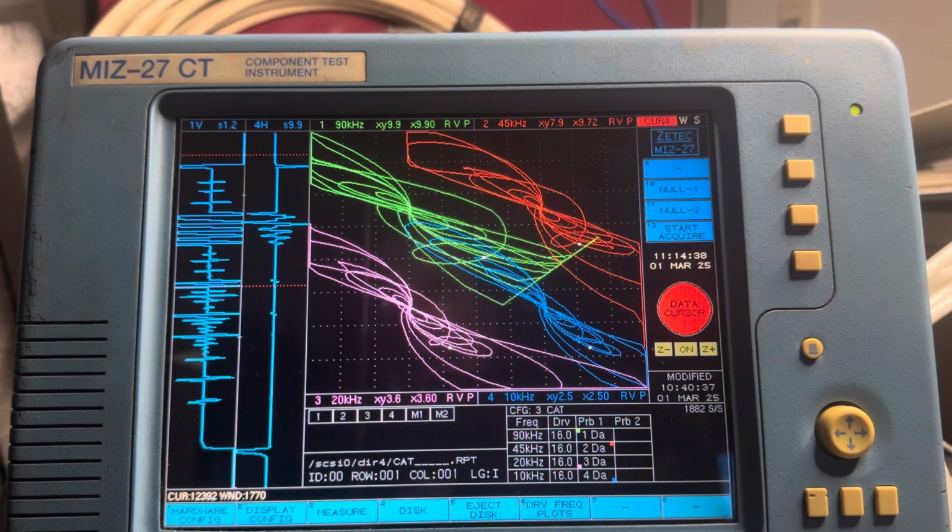The phase and amplitude of your signal is also related to the weighted average of all disturbed eddy currents at all depths. What that means is if you have an eddy current event right at the surface, you're going to have a signal with a phase angle that's closer to 0, or closer to probe motion, and it's going to be larger amplitude than if that same discontinuity was deeper in the material.